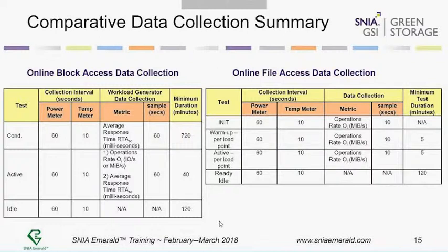I thought we were required to take the power measurement at least every 5 seconds. And so we've always been taking the power and then averaging it out over all 60 measurements to get a minute's worth. Yeah, you all have a custom tool, if I recall. Yes, and I thought we were doing that because it was required. If you could offer some clarification on section 7.2.9 of the spec, where it says power and voltage measurement shall be recorded to durable media using a period of not more than 5 seconds.